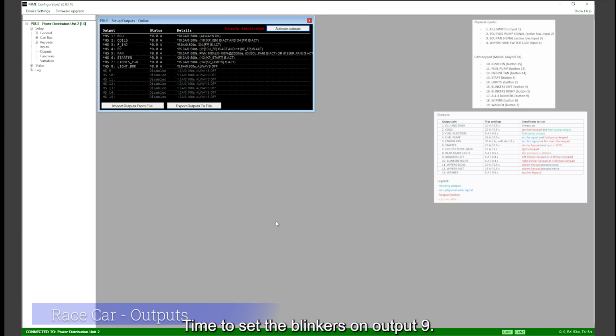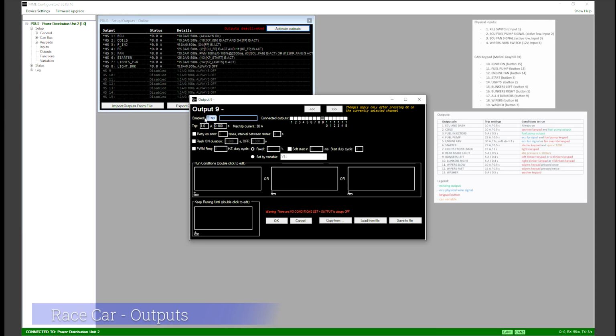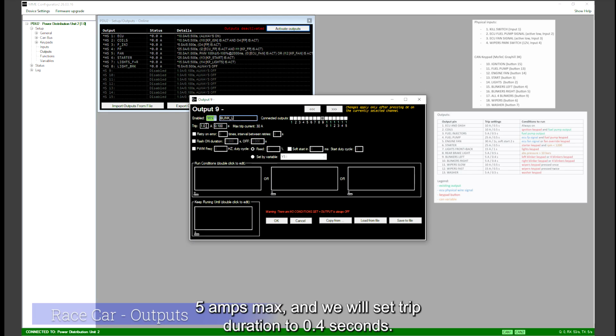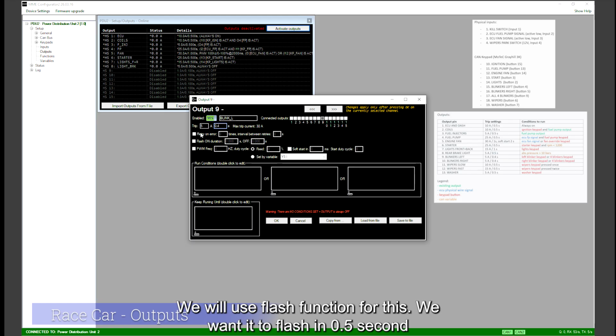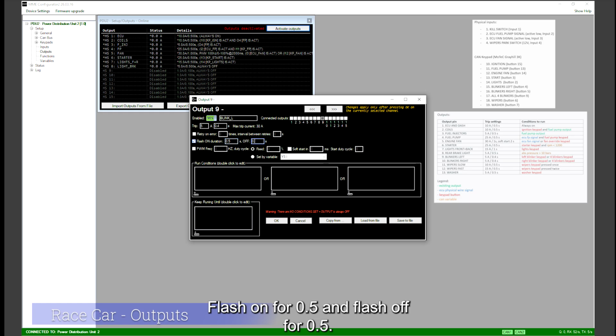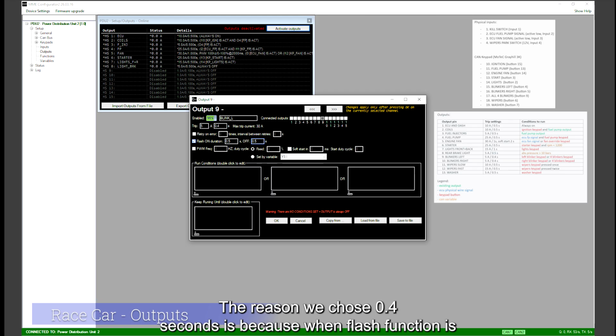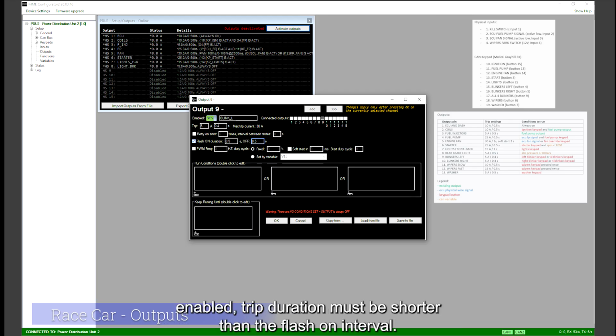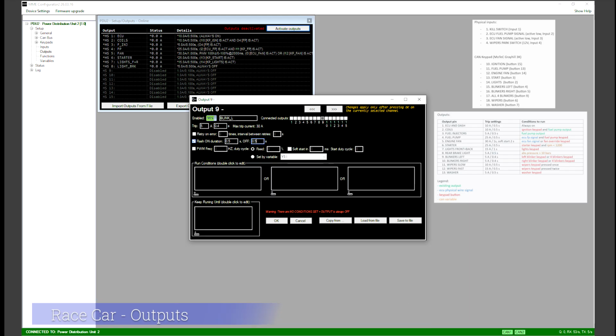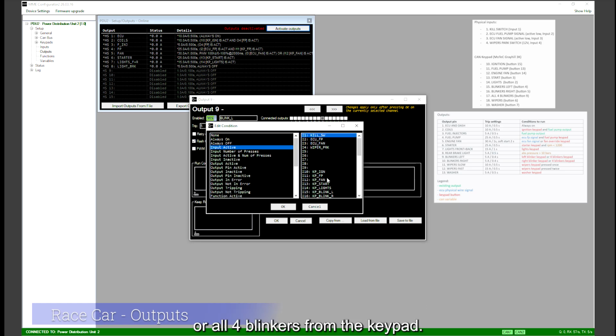Time to set the blinkers on output 9. Five amps max, and we will set trip duration to 0.4 seconds. We will use flash function for this. We want it to flash in 0.5 second intervals. Flash on for 0.5 and flash off for 0.5. The reason we chose 0.4 seconds is because when flash function is enabled, trip duration must be shorter than the flash on interval. Condition to run will either be left blinker keypad or all 4 blinkers from the keypad.